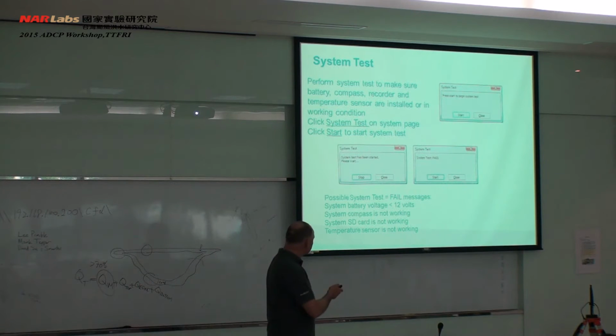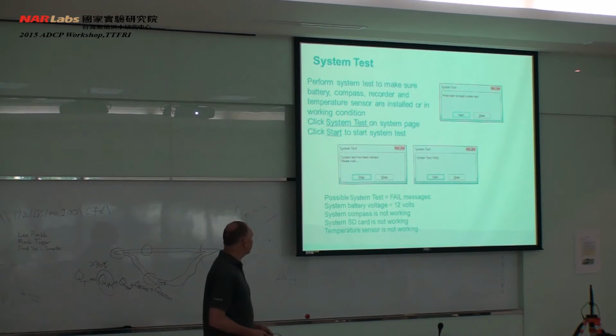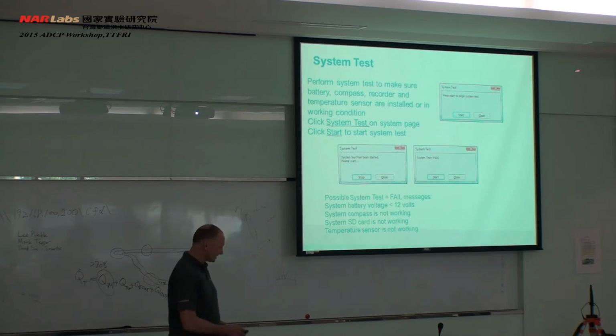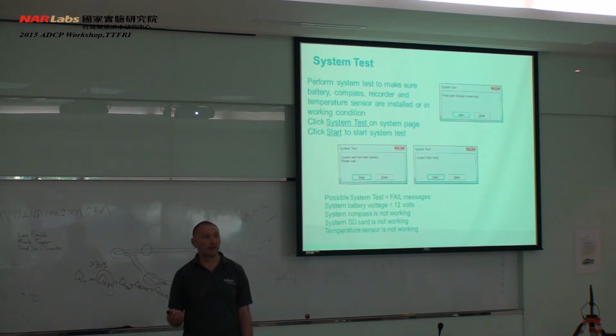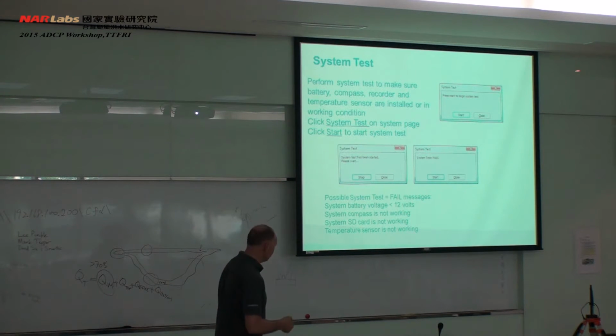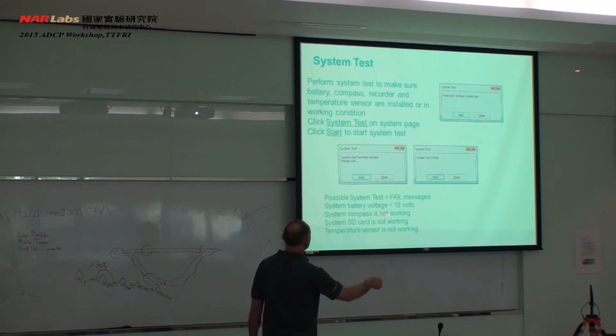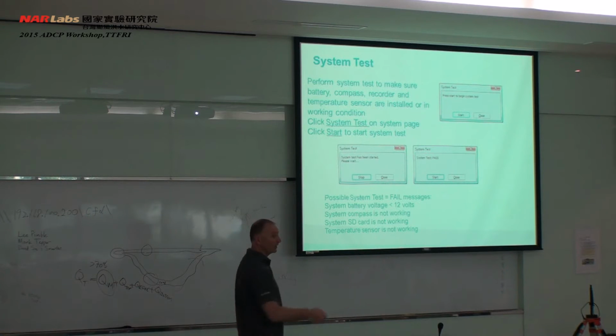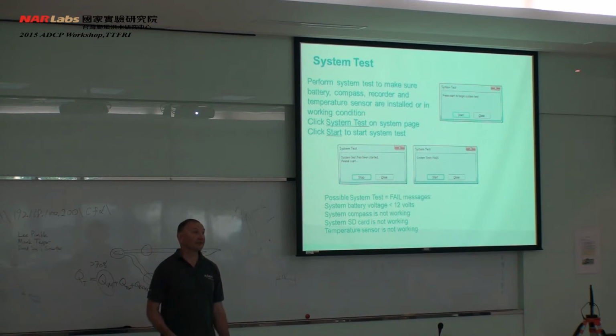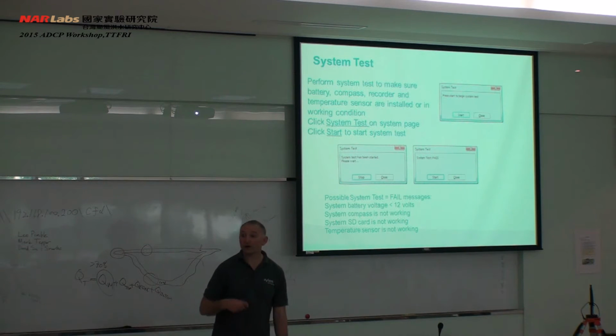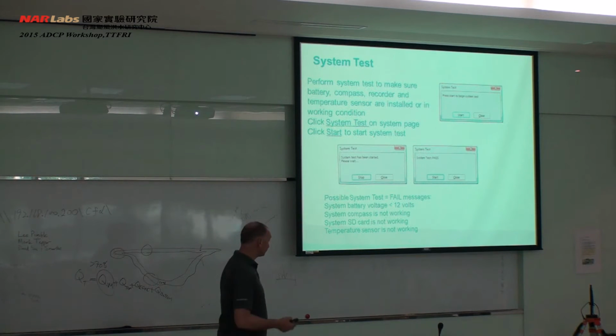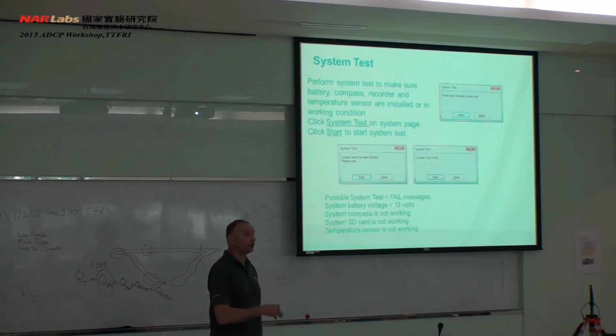Some of the possible system test fail messages that you get are: the system battery voltage is less than 12 volts, the compass isn't working, the SD card's not working, the temperature sensor's not working. There are some other ones, but these are the more common ones that you might see. I said about formatting the recorder on a regular basis. Particularly if you get this battery voltage less than 12 volts or the system compass isn't working, my first recommendation would be to format the recorder and then try your system test again, or just try connecting to it again. When you do a format of the recorder, it also does a hard reset on the instrument. So it will set all those features back to default, and we can start again.